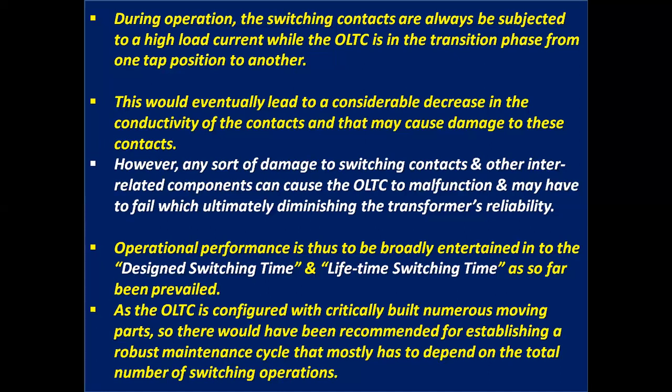As the OLTC is configured with critically built numerous moving parts, it is recommended to establish a robust maintenance cycle that mostly depends on the total number of switching operations.